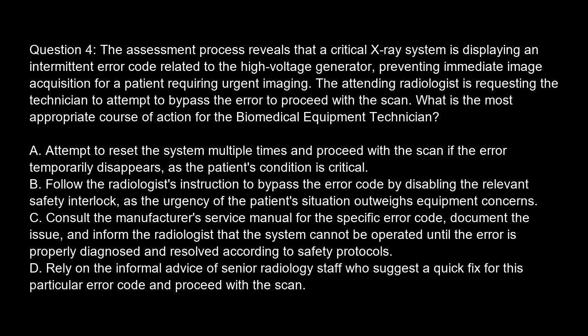Option C. Consult the manufacturer's service manual for the specific error code, document the issue, and inform the radiologist that the system cannot be operated until the error is properly diagnosed and resolved according to safety protocols. Option D. Rely on the informal advice of senior radiology staff who suggest a quick fix for this particular error code and proceed with the scan.